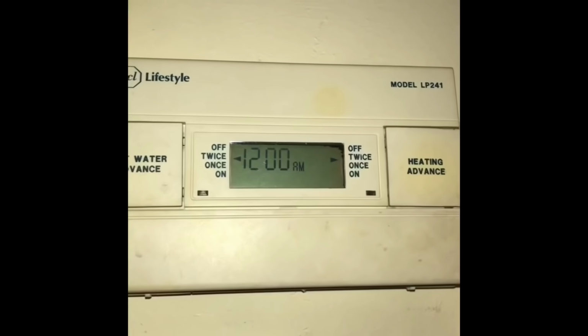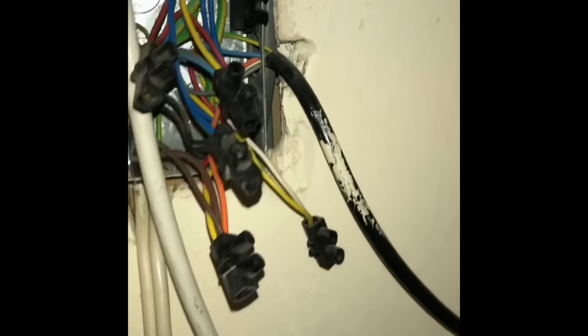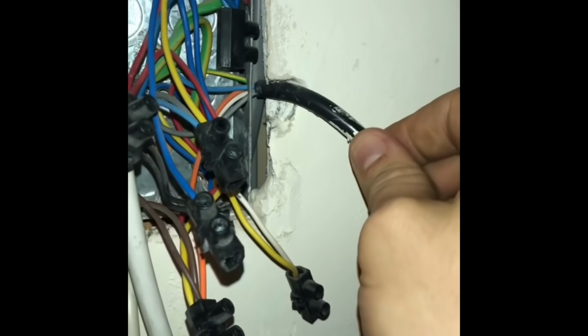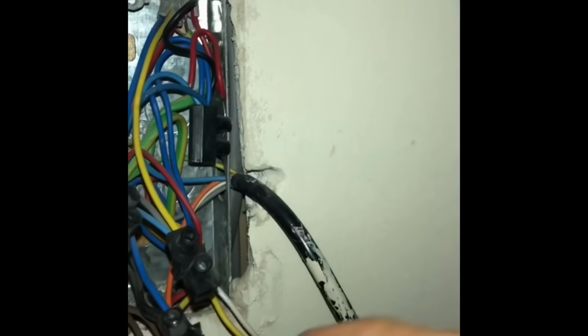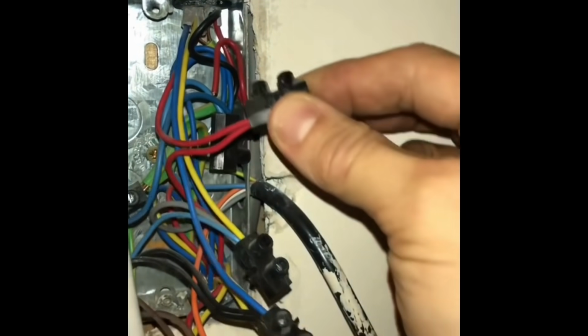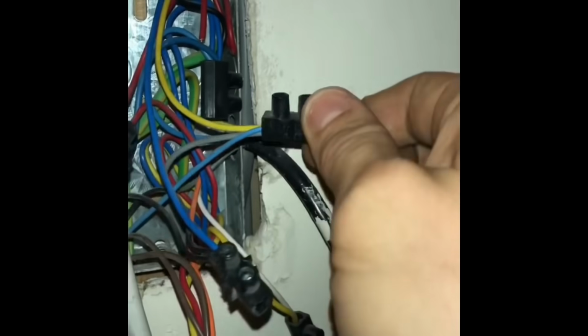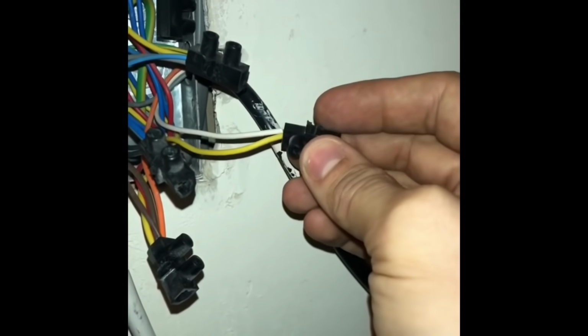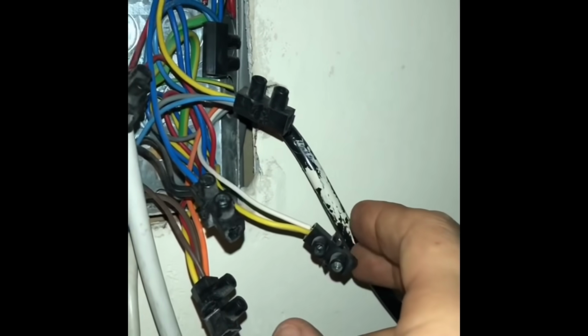What's up guys, it's PB back with another 60-second fault finding tip. So I've been called to this job with no central heating. Now the method that works best for me is to work out what cable feeds what component part, and then in a series, starting at the programmer, work out which part's doing its job and which part's not to identify the fault. So I'm going to start at the programmer on this one.